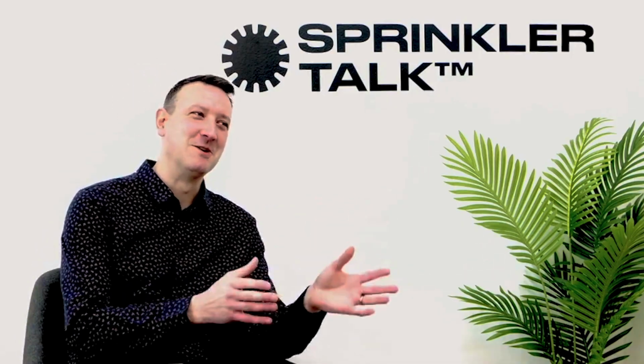Jake, my question to you is, how do we integrate that system into the wider strategy? How do we link it to fire alarm panels or BMS systems, etc.? Yes, this can be done in multiple ways. Our Zone Check Addressable controller has basic fire and fault relays. Nine times out of ten, our controller will be mounted right next to a fire alarm panel. Our system will get a fire signal and it will say on our panel, you've got a fire at zone 3, left staircase or something like that. That signal then gets passed over to the fire alarm panel, but because it's basic relays, it will just say fire.